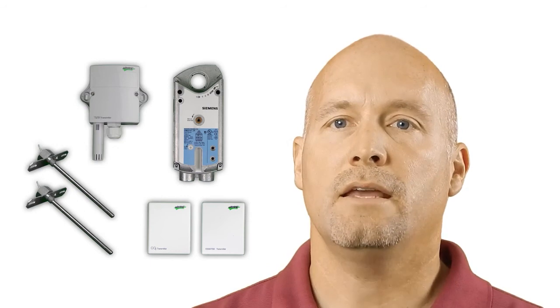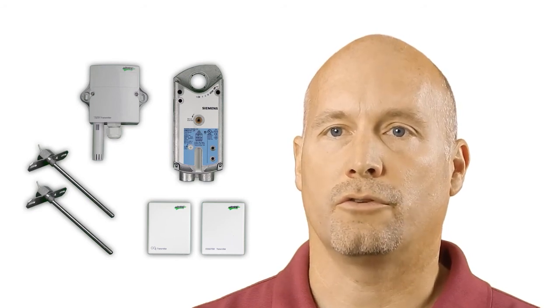But the ultimate benefit of this system is that it should be the lowest cost factory alternative in the market. This happens because we do not use a proprietary communication network, and our system utilizes standard sensors and actuators like a 24-volt actuator with feedback, 10K NTC Type 2 thermistors, standard humidity, CO2, and VOC sensors.